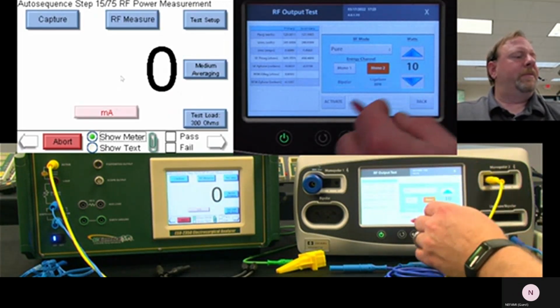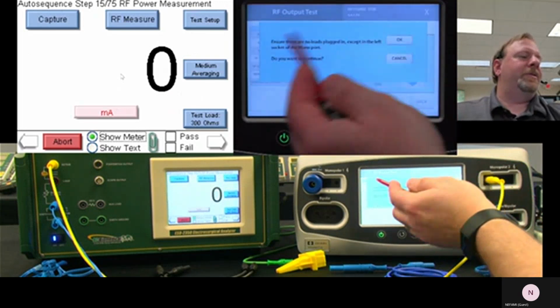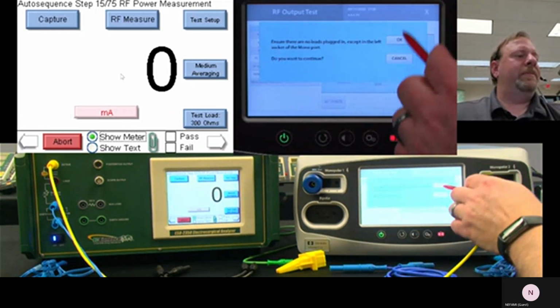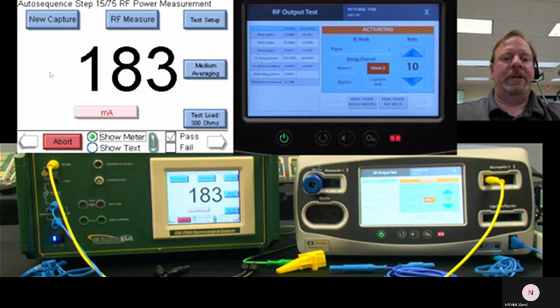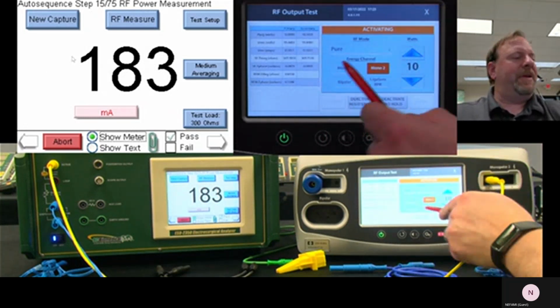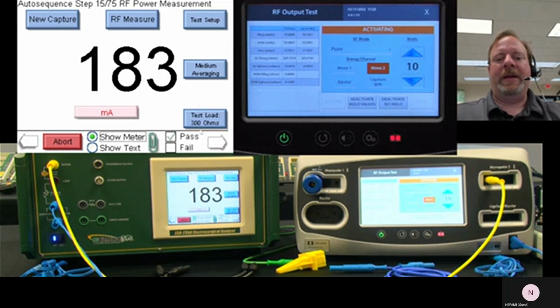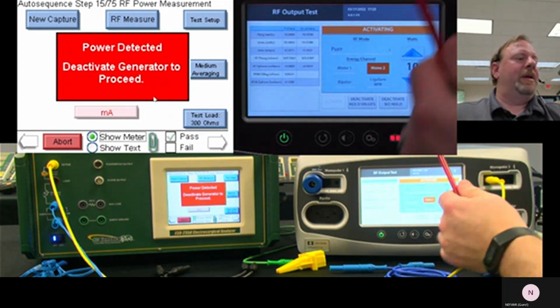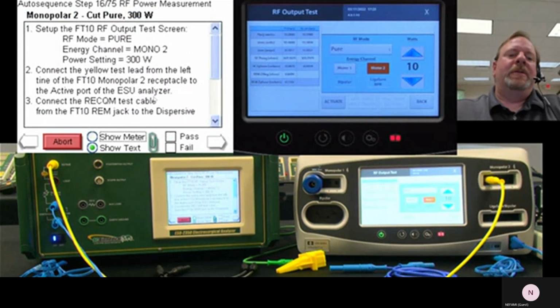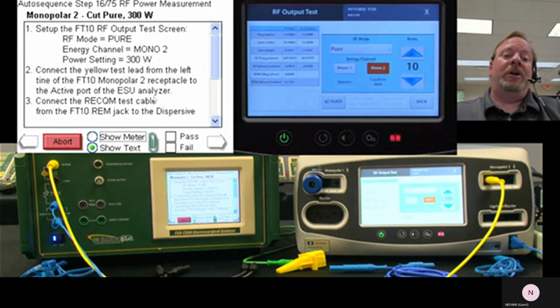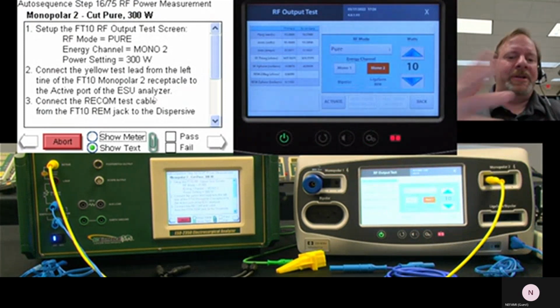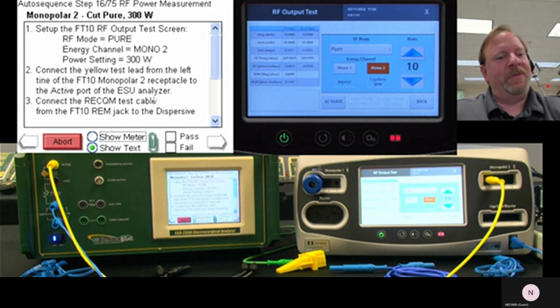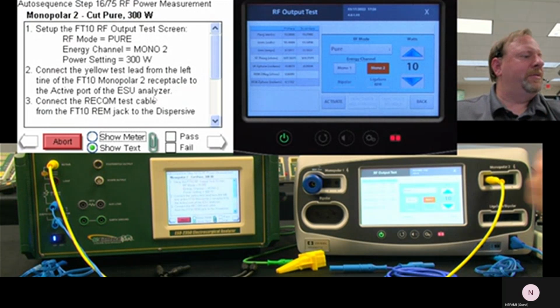So I'm going to show my meter, activate. Now it's saying, are you sure you have the right cable plugged in? Yep. Thank you very much. Get my output, and it's good. Now what happens if I forget to deactivate the generator and I say, okay, let's just move on? Oh, power's detected. So deactivate your power, and then it will allow you to move on. So it's trying to safeguard itself from trying to switch loads while the power is active. And that's the 2350. So it knew there was current there, and it's like, I'm not going to move on until you deactivate the generator like I told you to.